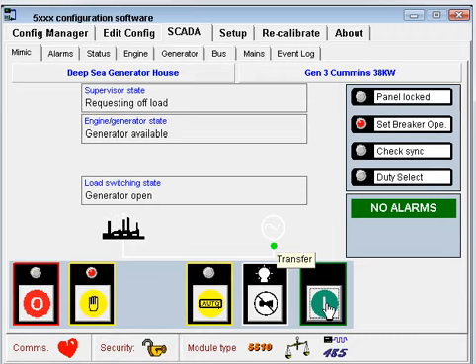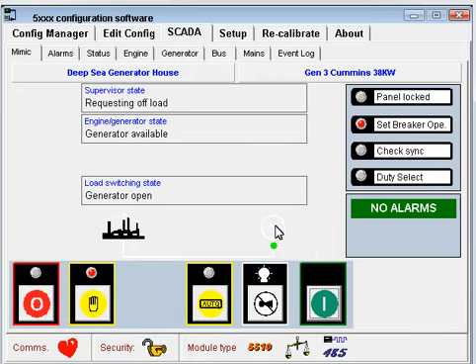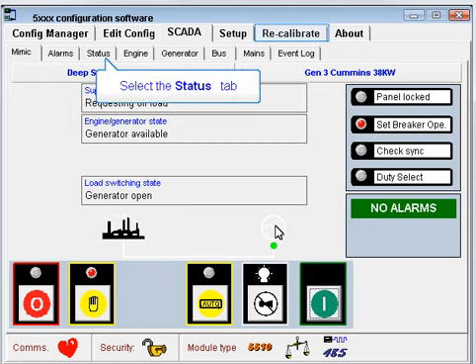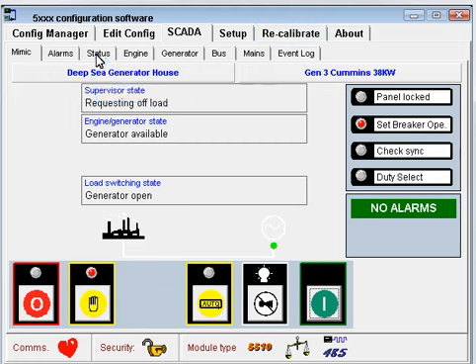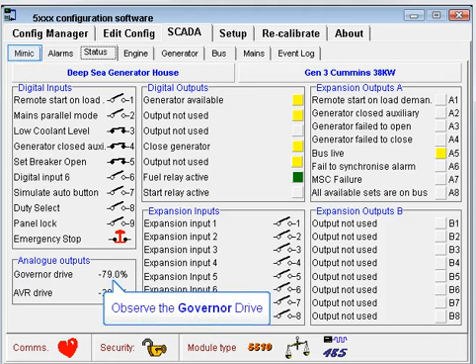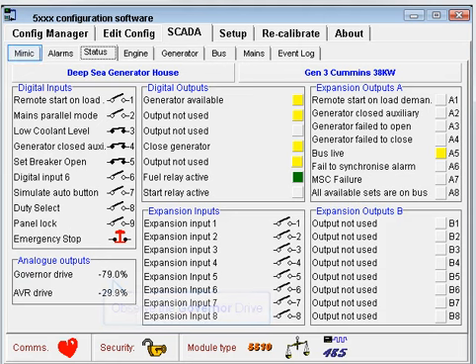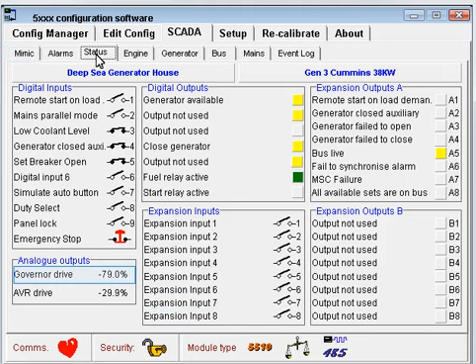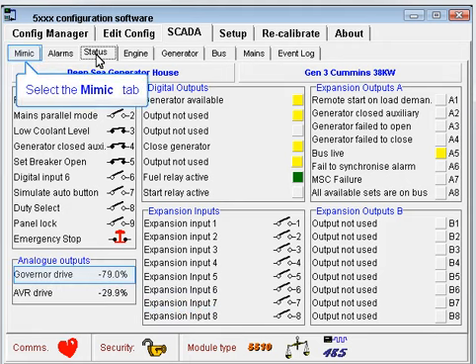Check that the generator lowers in speed to the new setting, and use the SCADA status display to check the governor drive. If necessary, trim SW2 for the governor setting to bring the governor drive to around 80%. Use the MIMIC page to stop the set.